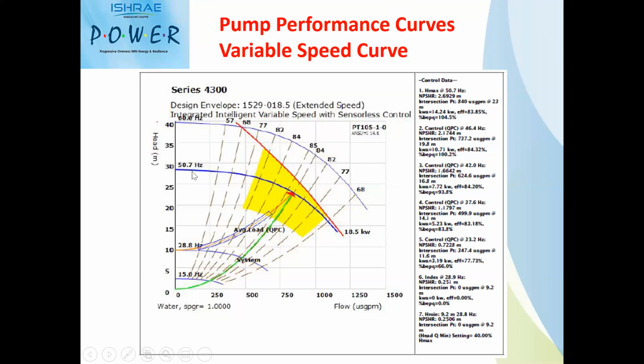Suppose you reduce the RPM from here; typically it is operating at 50.7 hertz. Suppose you require lesser flow, lesser head based on your load. Say your load is 80%, you don't require this design duty parameter. So in this case, typically the pump should operate maybe at 46.2 hertz, which will be drawing a particular lower flow and lower head. Similarly, when we are referring to any variable load pump curve, we will have various points wherein you will have part load, flow and head, as well as efficiency data being plotted by all the pump manufacturers.